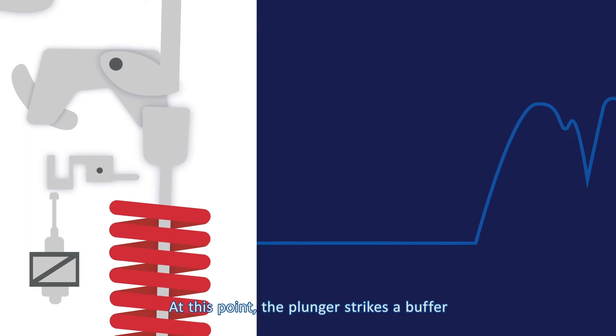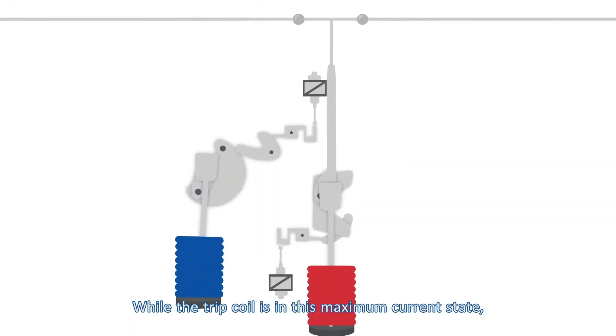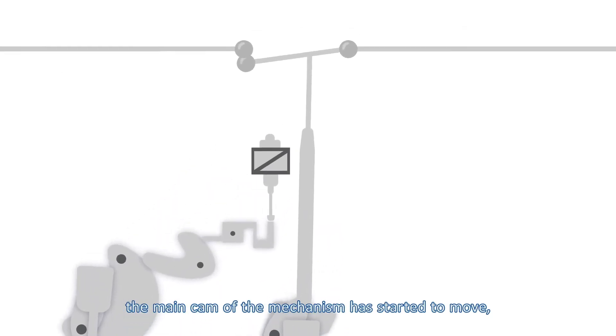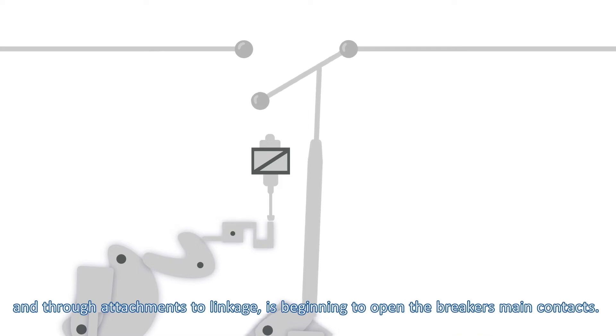At this point, the plunger strikes a buffer and begins to rise until maximum current is achieved. While the trip coil is in this maximum current state, the main cam of the mechanism has started to move and through attachments to linkage, is beginning to open the breaker's main contacts.